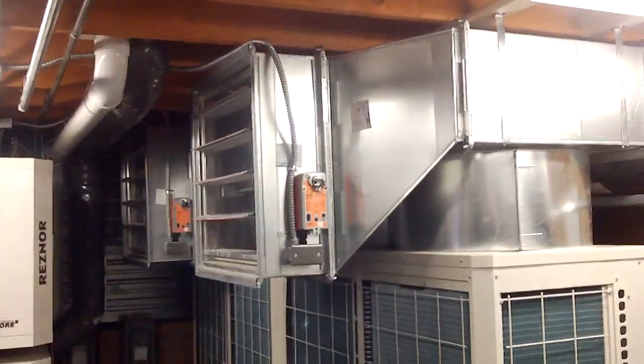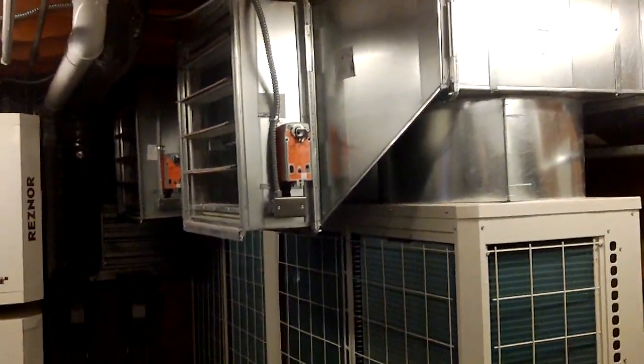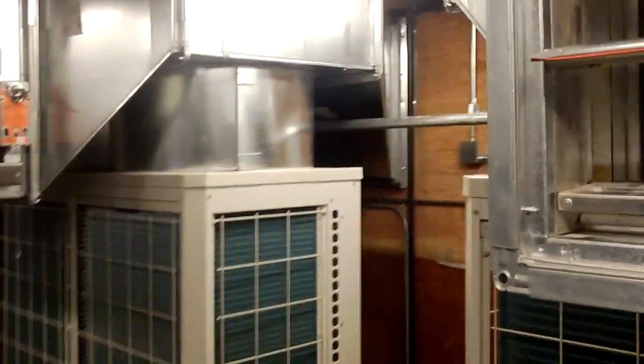If we are actually cooling the building — there are actually 8 of these units up here in this room — if some of the units are in cooling mode, then it will recirc the air back into the room to be absorbed by one of the adjacent units that may be in heating mode.